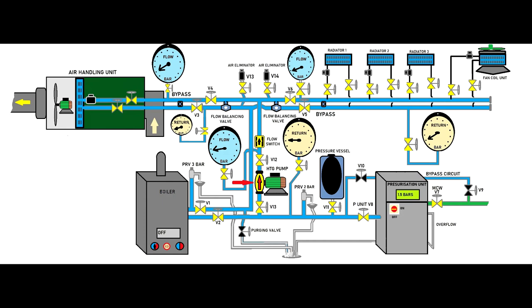Once the pressurization unit sets the pressure correct into the system, it will start the heating agent circulating pump, and then the pressurization unit will push a little bit more water into the system to cover the difference between the return when the pumps are not running with the return when the pumps are running. So that will be the true pressure readings onto the pressurization unit display.